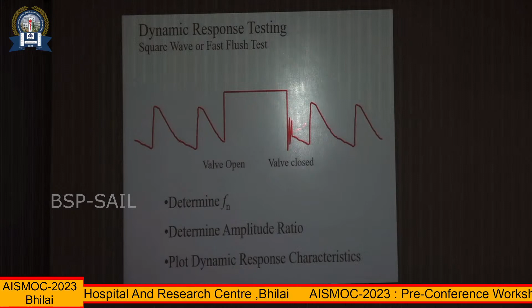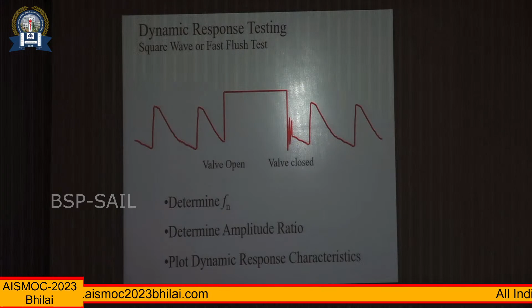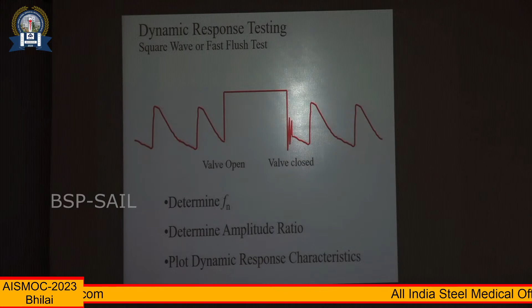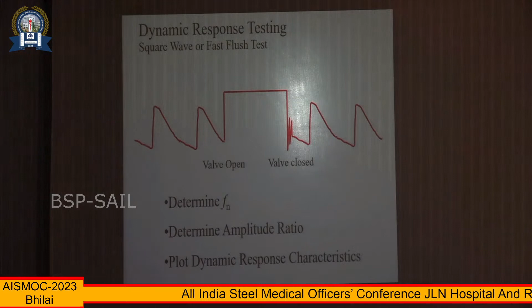Okay, so you calculate the number of waves and you have the ratio of the second wave to the first wave. We call it D2 by D1, and the ratio has to be at least 0.6. We call it the damping coefficient. If the ratio of the second to the first wave is 0.6, that is optimally damped. You do not want a system which is underdamped, and you do not want a system which is overdamped. You want an optimally damped system, and you can test it by doing the fast flush test.